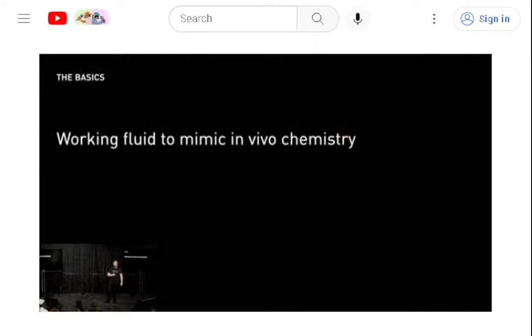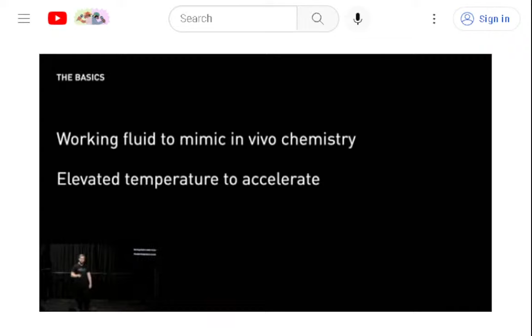So how does the system work? Well, at a very basic level, it comes down to three things. First, we want to mimic the internal chemistry of tissue. Next, we want to accelerate these chemical interactions as well as diffusion with our implant materials. And finally, we want to aggressively cycle the internal electronics of our implant. With these things, primarily the first two, we have achieved a conservative 4x acceleration factor by the Arrhenius relationship. In other words, every day our implants spend in our accelerated system is equivalent to at least 4 days spent in vivo.